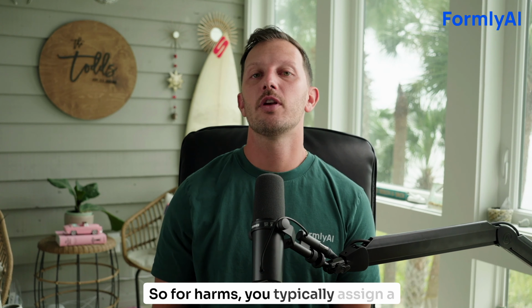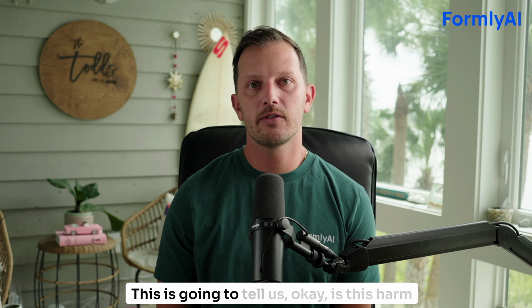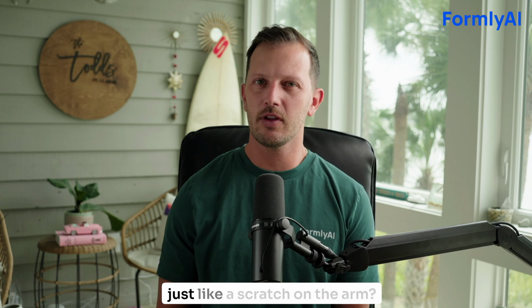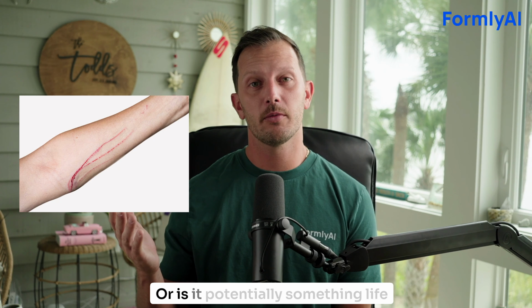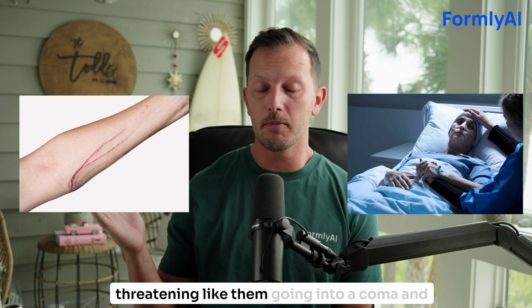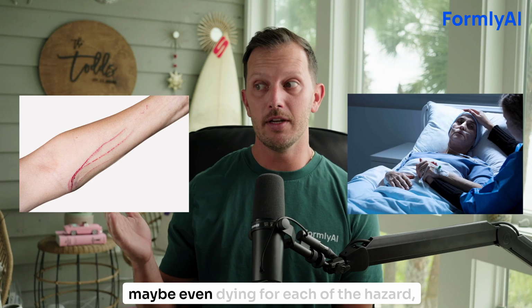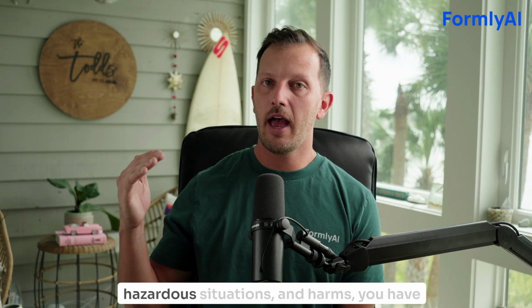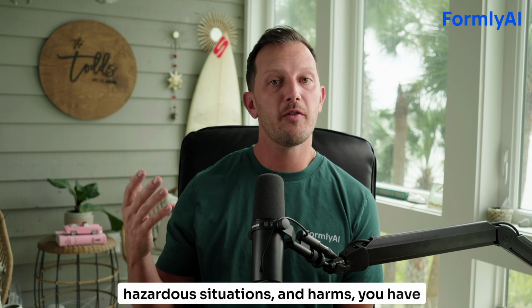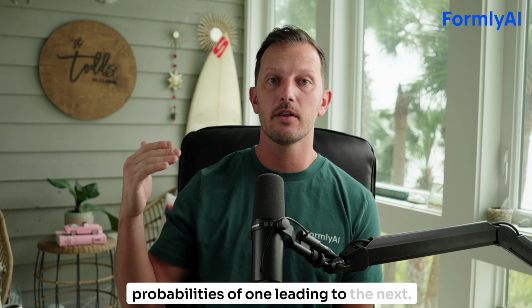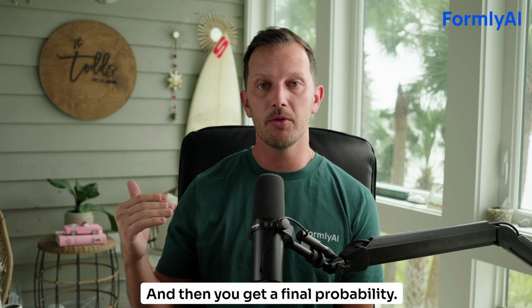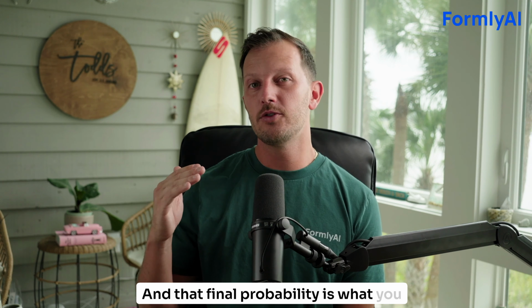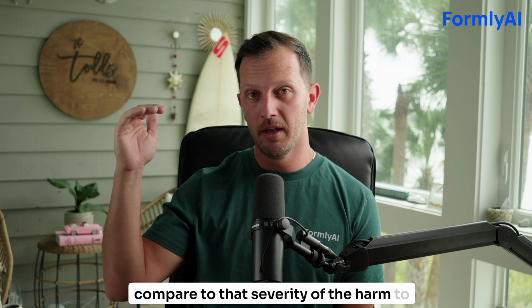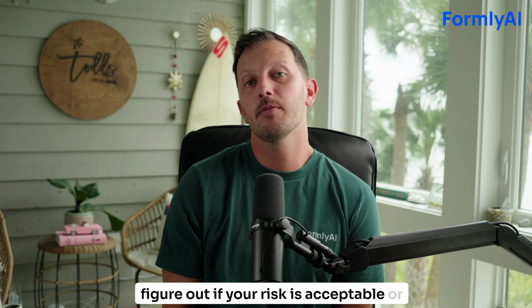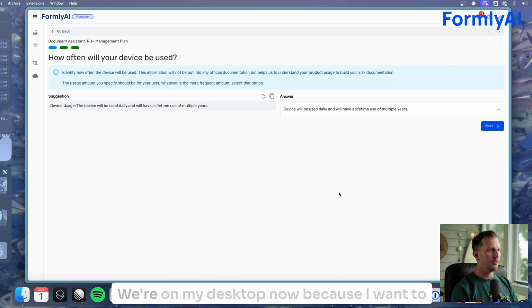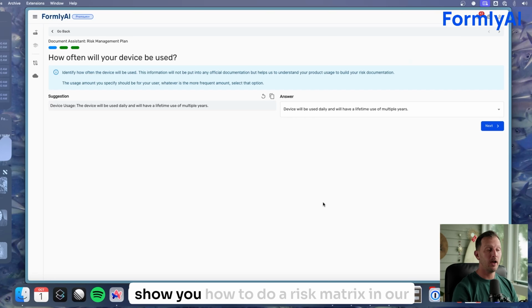So for harms, you typically assign a severity. This is going to tell us, okay, is this harm just like a scratch on the arm, or is it potentially something life-threatening, like them going into a coma and maybe even dying? For each of the hazardous situations and harms, you have probabilities of one leading to the next. And then you get a final probability. And that final probability is what you compare to the severity of the harm to figure out if your risk is acceptable or unacceptable.